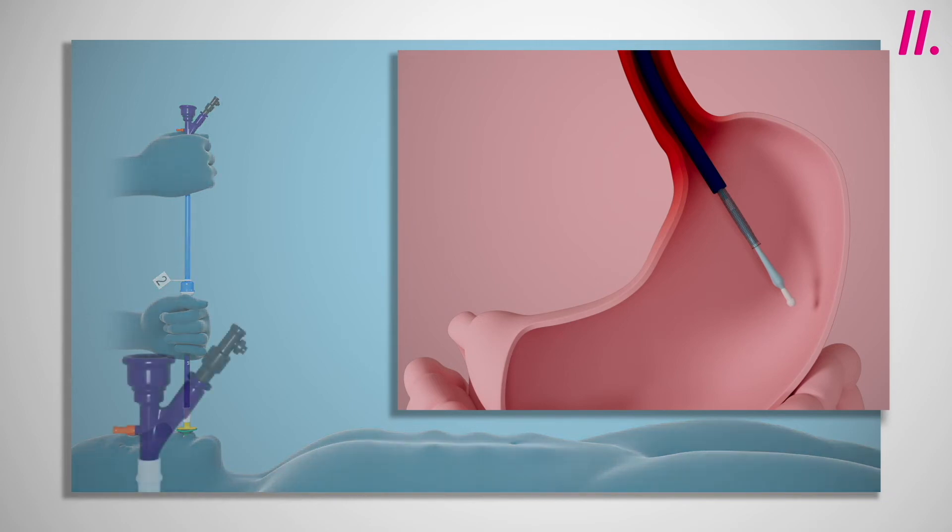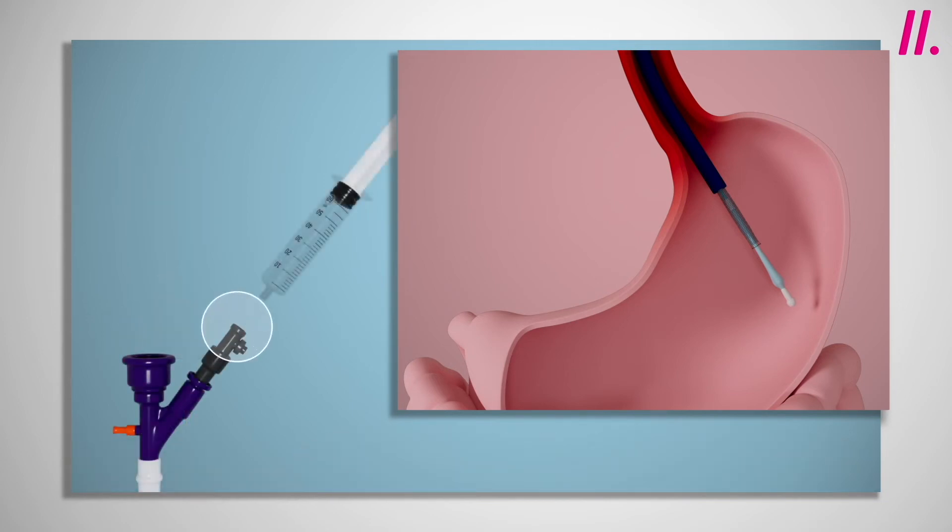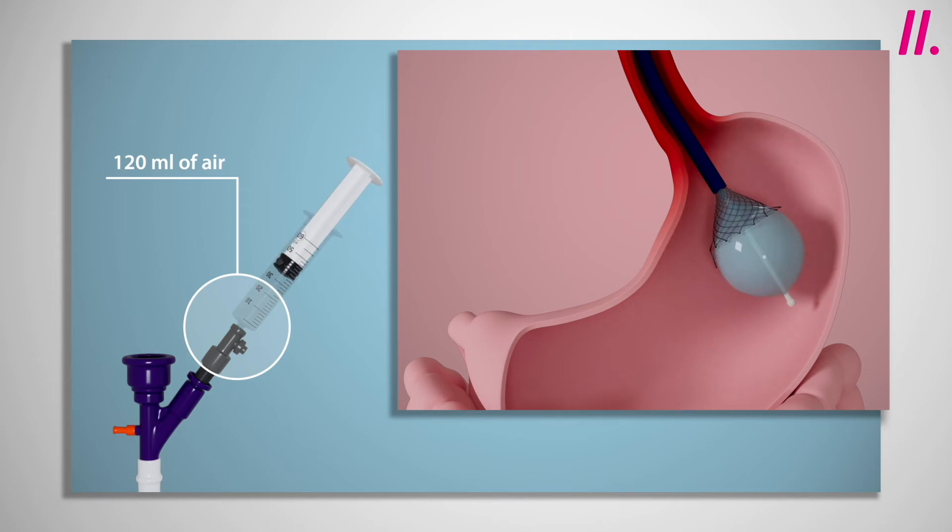120 ml of air should then be used to inflate the balloon. The balloon valve is one way and allows the 60 ml syringe provided to simply be pumped twice, without need for removing in between.